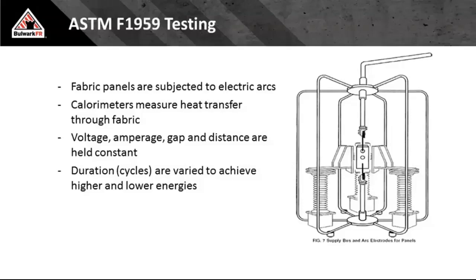Well, the ASTM F1959 test methodology is how we come to an ARC rating. An ARC rating is communicated in one of two ways. You have an ATPV, an ARC thermal performance value, or you have an E sub BT, energy break open threshold. Real simple: either the fabric is intact and I get a second degree burn through the fabric, or the fabric starts to fail and I assume a second degree burn at failure. Those ARC ratings are then communicated in the label.